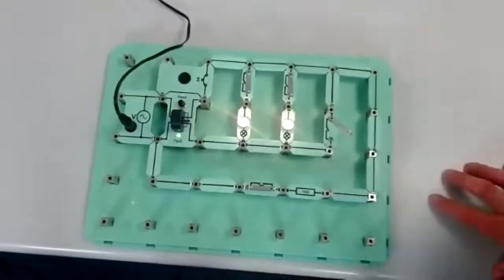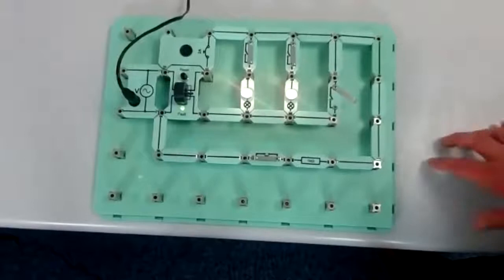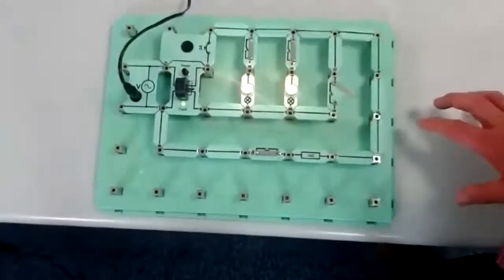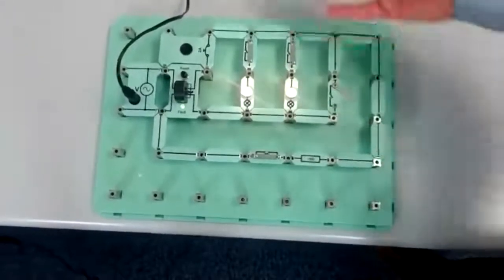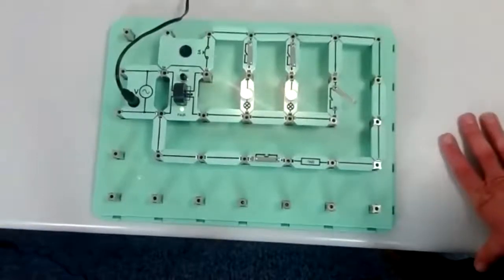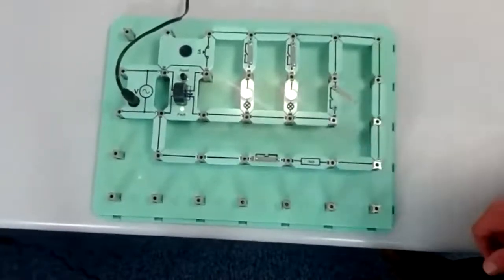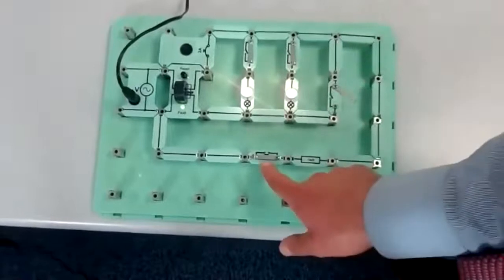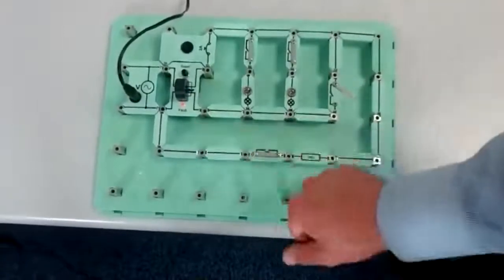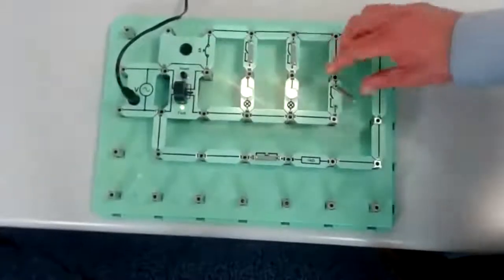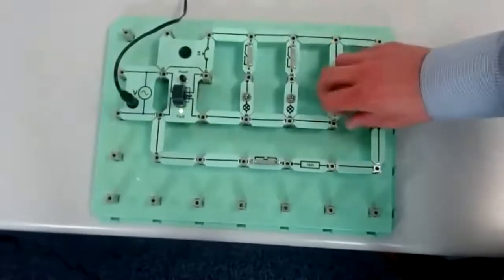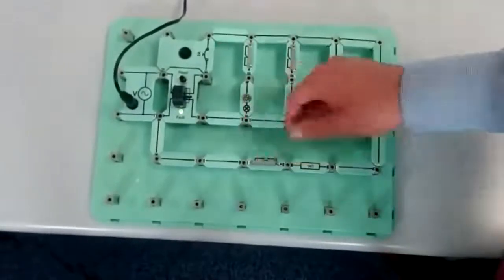And this is part of the level 2 kit, okay? So this is just a nice experiment that in reality is quite a hard thing to teach, how an RCD and a fuse board works. One more time: if there's a leakage, the RCD trips, but the fuse board doesn't. If there's a short circuit, the fuse board trips, but the RCD doesn't.